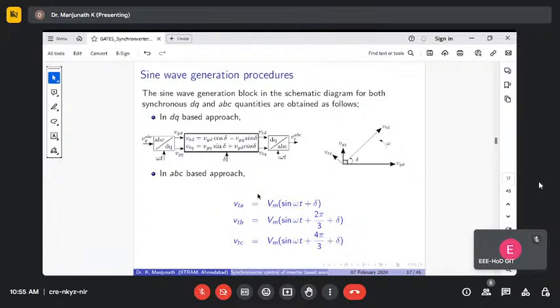When we go for DQ based computation, what is phase shift delta? Delta phase shift is the phase shift between two voltage phasors. One is terminal voltage of VSC, another one is grid voltage. So this phase shift is delta. We have to realize the horizontal and vertical component of delta, horizontal component being cos delta and vertical component being sin delta.